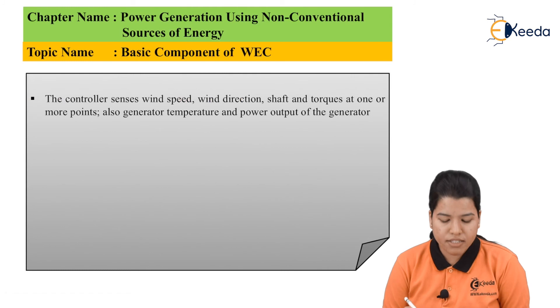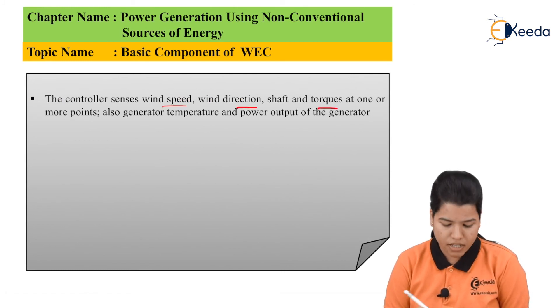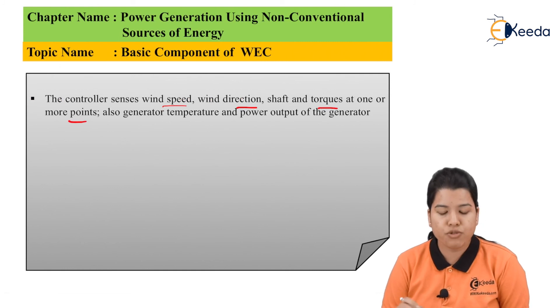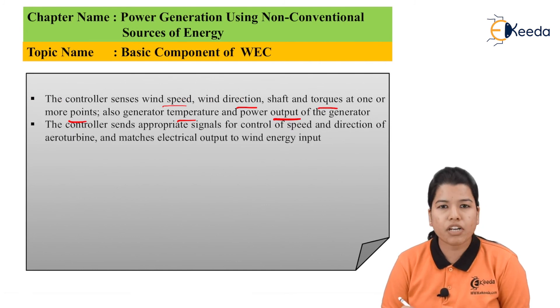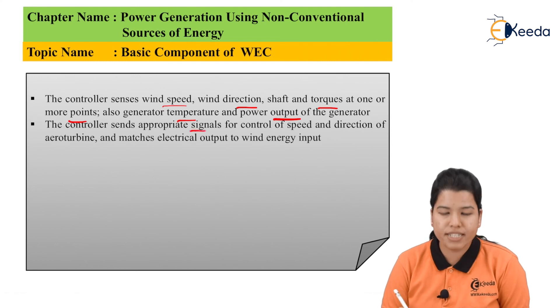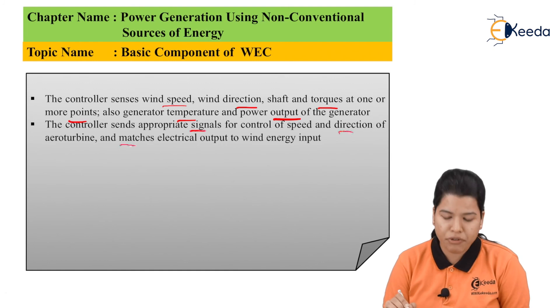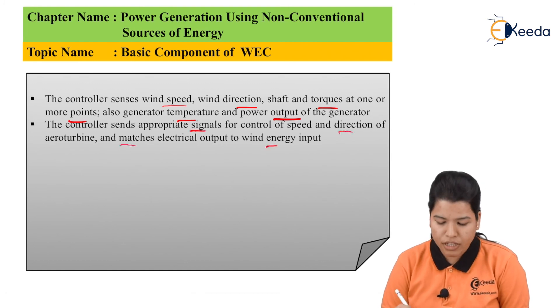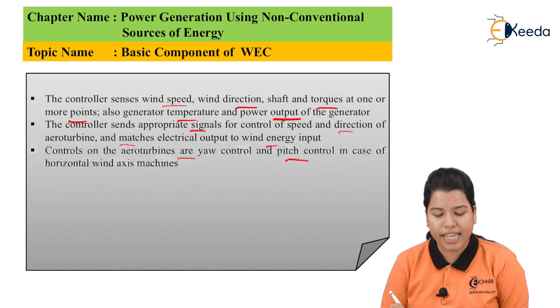The main function of the controller is to sense the speed of the wind, then wind direction, shaft and torques at one or more points. Also, the generator temperature and the power output of the generator are sensed by the controller. The controller will send the appropriate signal for the control of the speed and direction of the aero turbine, then it will match the electrical output to the wind energy input. Controls on the aero turbine are the yaw control and the pitch control in case of horizontal wind axis machines.